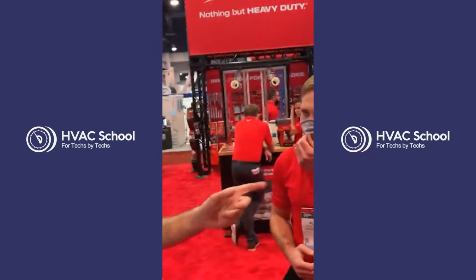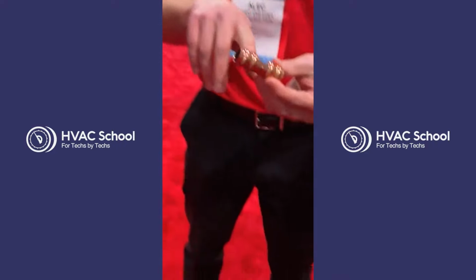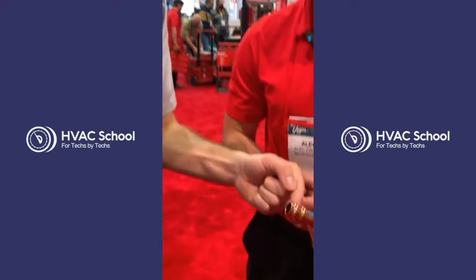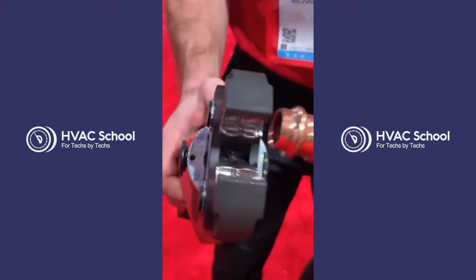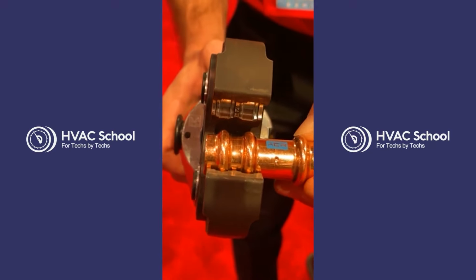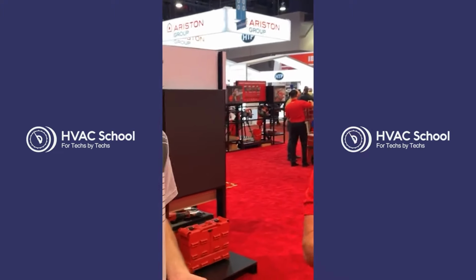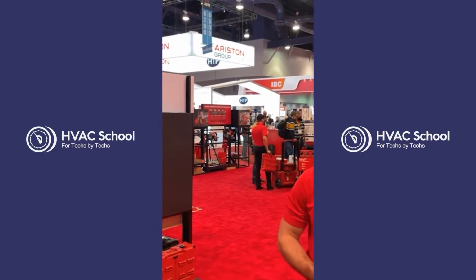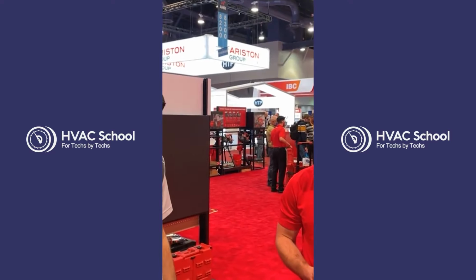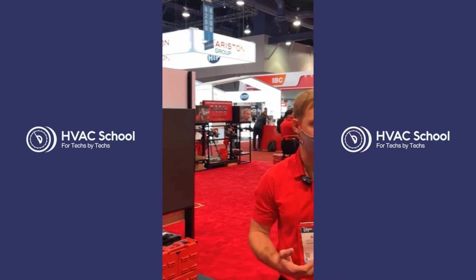That's a pretty neat fitting, I'd never seen this one before. It's a little different from others out there. It has a double O-ring but is still a single press. It actually has a triple jaw in the press that presses on the outside of both O-rings and in the middle between them. You can see how the fitting sits properly right into the grooves of the jaw, so it's really easy to align. That's hard to screw up on alignment, which is what I see a lot of people struggle with on their first time using a press, misaligning the fitting and not pressing it properly. This makes it more foolproof, and the double O-ring is nice too. It's a flameless, faster, and consistent alternative to braze connections.